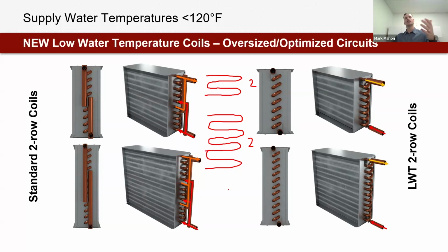And the important thing to know is how much capacity do we need for the zone? From a fundamental perspective, if we think about the sensible heat transfer, air side and water side equations, a certain GPM at a certain delta T equals a certain CFM at a certain delta T. All we're doing is taking that hot fluid and moving that energy to air, and we get hot air. So what we see with these types of systems is we really want to live in the 1, 2 or 3 GPM range. And so we've optimized the coil with all of those considerations in mind. This is a massive system of equations where all these different elements push and pull and play with one another.